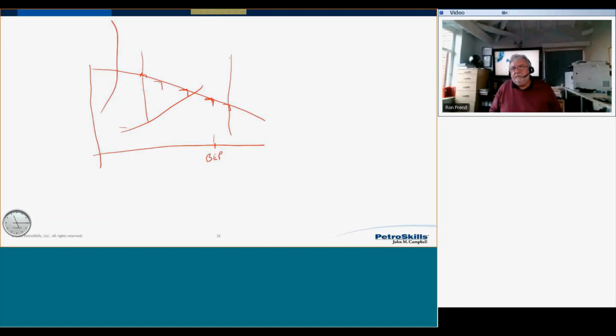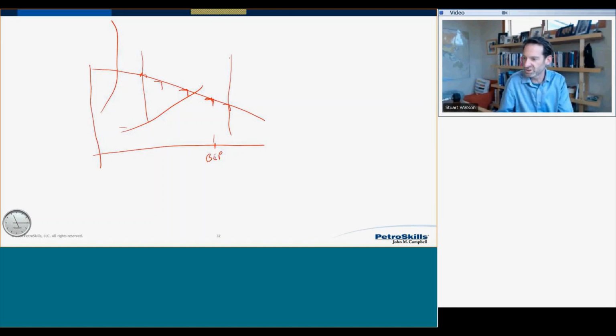So there's another question. I'm going to jump question, as I think we're rapidly running out of time. Yeah, we are. That happens. Another question here, on NPSH available, and I'm not sure if you just want to focus on that or that and pump head and pump performance. We do all calculations considering density, SG, based on the pumping fluids. However, NPSH calculation is based on water. How does that vary the performance of the pump when the density is changing? When you have an NPSH curve based on water and you're pumping crude oil, does that affect your NPSH curve?